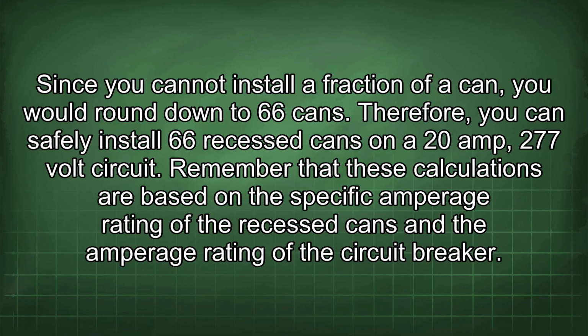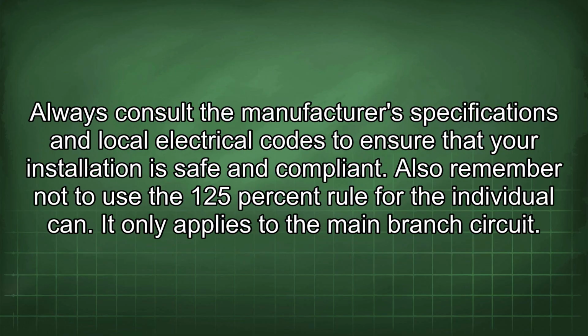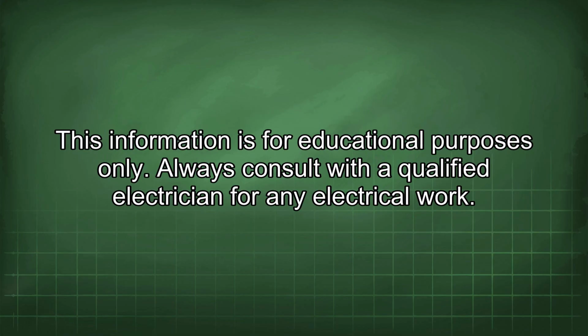Remember that these calculations are based on the specific amperage rating of the recessed cans and the amperage rating of the circuit breaker. Always consult the manufacturer's specifications and local electrical codes to ensure that your installation is safe and compliant. Also remember not to use the 125% rule for the individual can. It only applies to the main branch circuit. This information is for educational purposes only. Always consult with a qualified electrician for any electrical work.